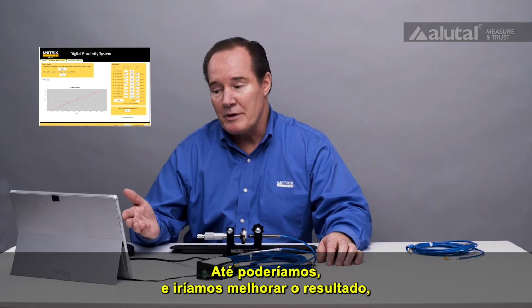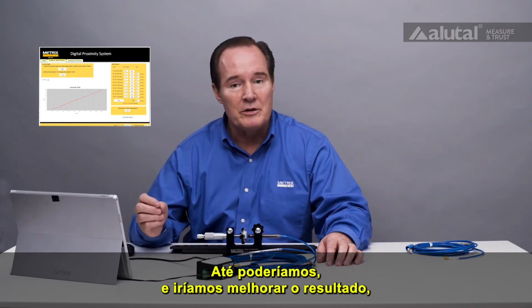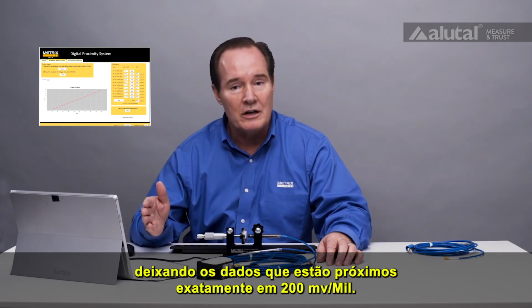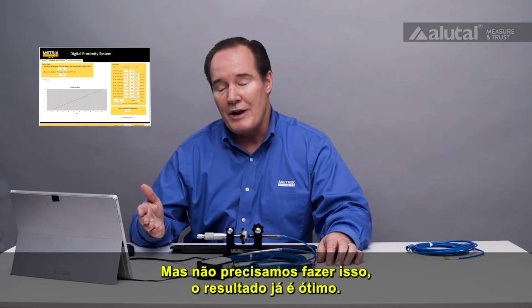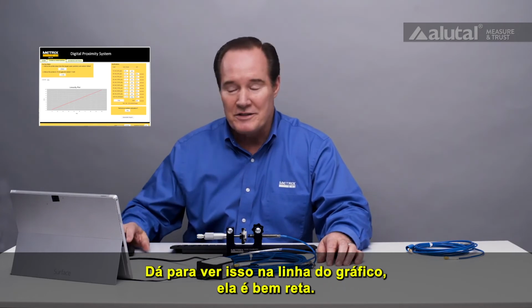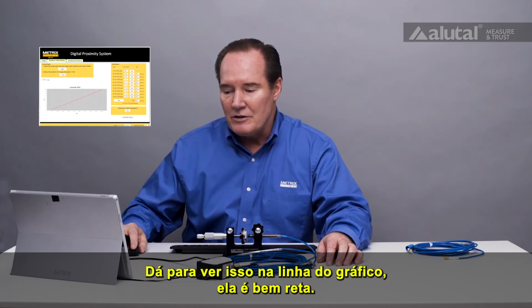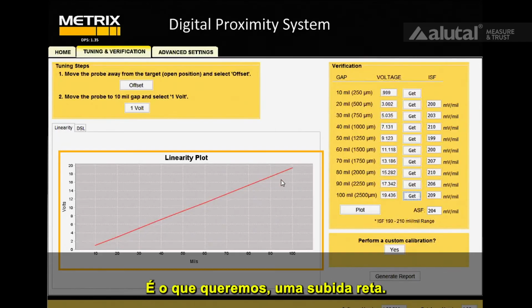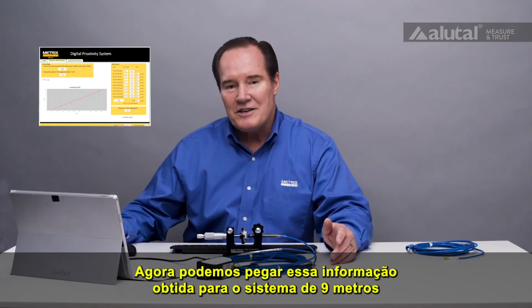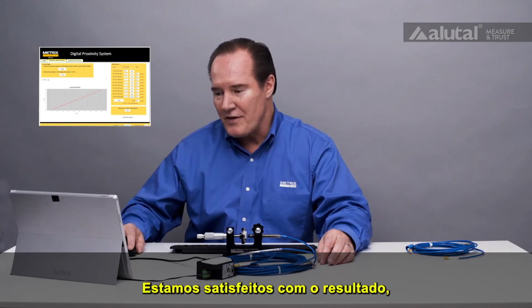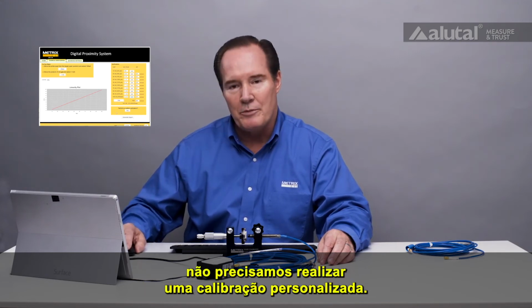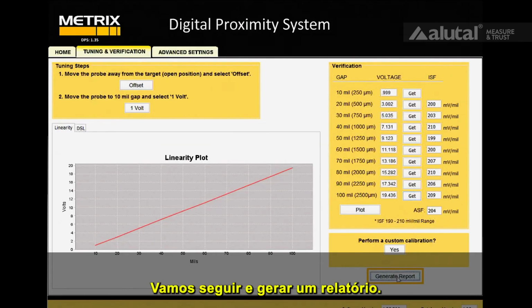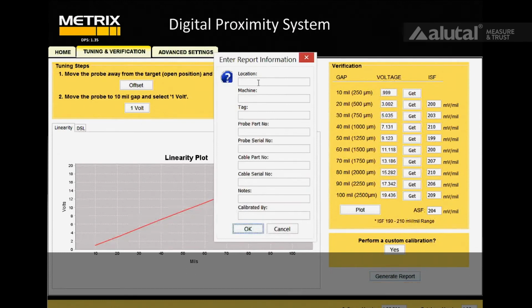We could run a custom cal, and we could see that we might be able to improve it, get those points that were close to the boundary, right on 200 millivolts per mil, but we really don't have to. This is actually very straight, and you can see that in the graphical line, very straight line. That's what we want, nice straight slope. And we can take this information that we have with this 9-meter system and create a report. So we're satisfied with it. We don't have to perform a custom calibration. We're going to go ahead and generate a report.